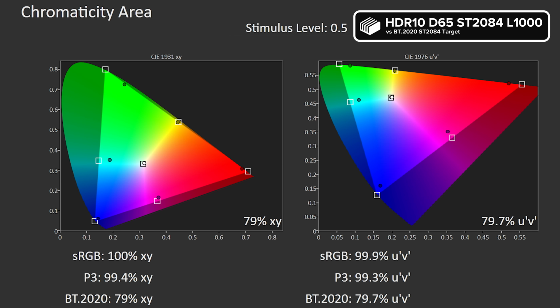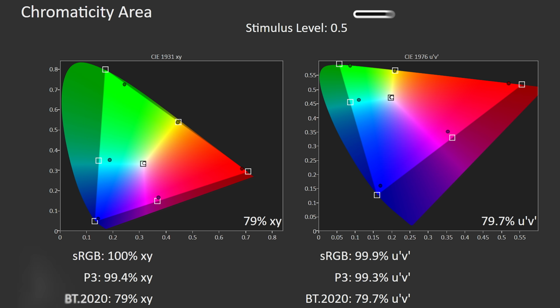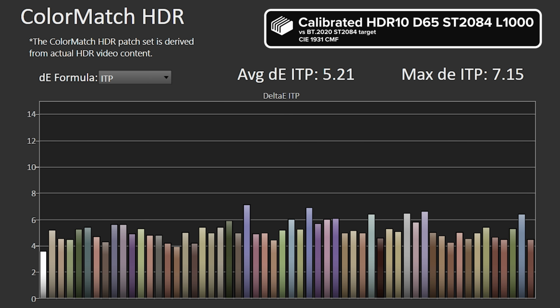Moving over to HDR, we were able to hit 79% of the BT.2020 color space, which is still really good. In terms of color accuracy in HDR, we hit a Delta E ITP of 5.21, which also is very good. We were talking about Delta E 2000 of less than 2 being what you want. Delta E ITP is a completely different scale, so it doesn't really match up, but a good score in Delta E ITP would be around the 10 range. So being at a score of 5.21 is incredibly good. It's getting close to what you'd expect for mastering, which is 4 and below.